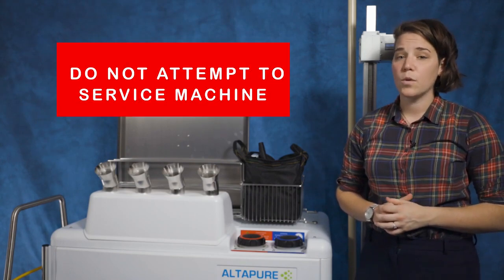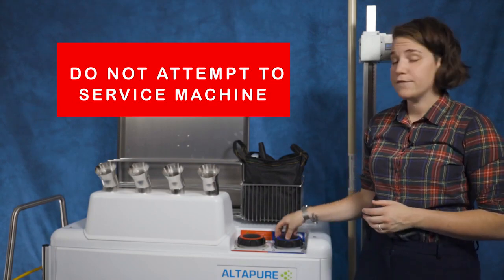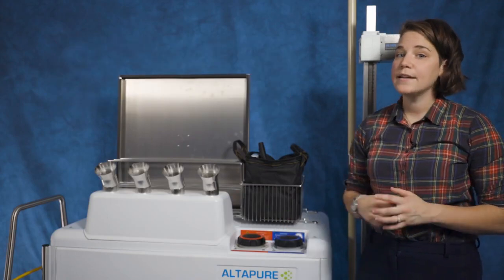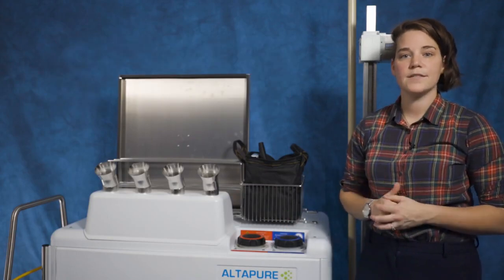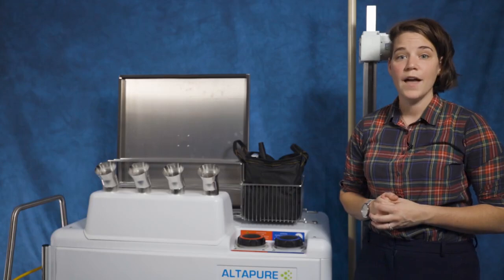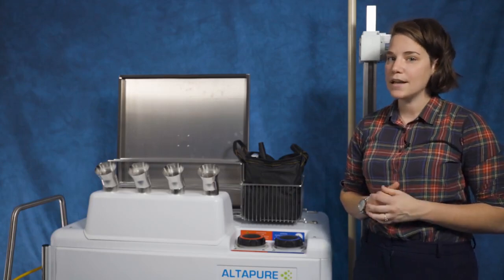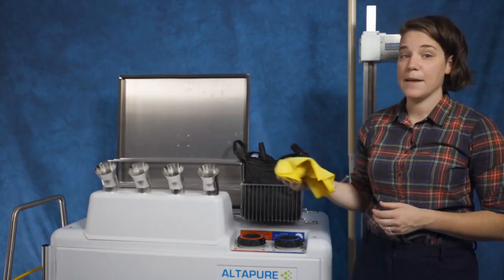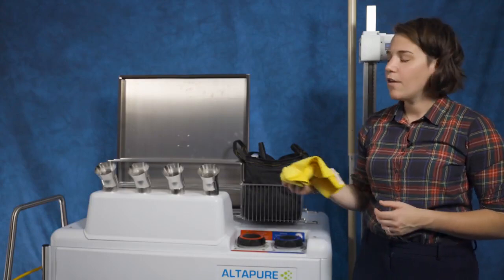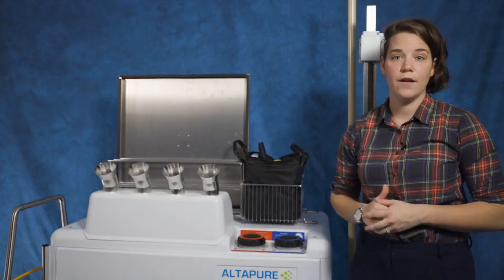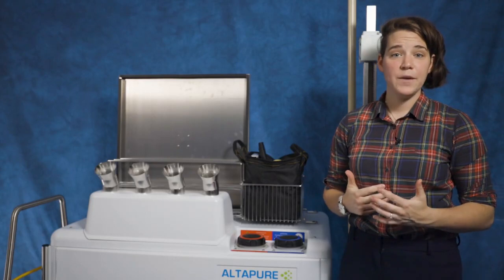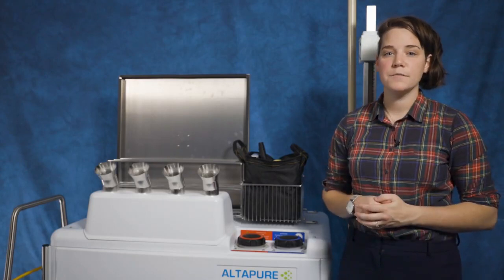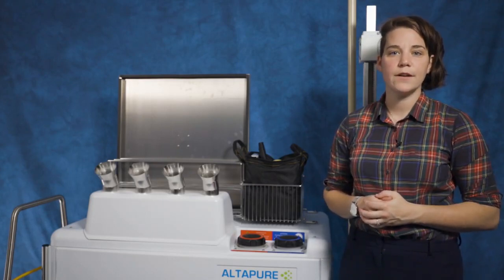The only maintenance required of you is maintaining the fluid levels. The machine does not need to be disinfected, as it disinfects itself every time it's used in a room. However, if the machine does get dusty or dirty, wipe it down with a damp microfiber cloth. All other maintenance shall be done by a certified Altapure service technician. Now that we have a good understanding of the equipment of the machine, let's move on to a typical cycle protocol.